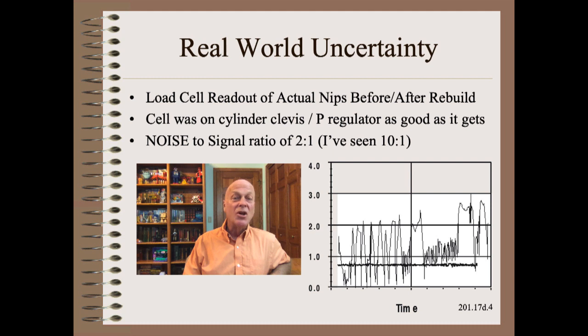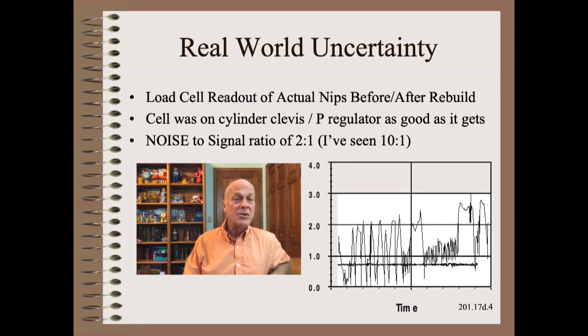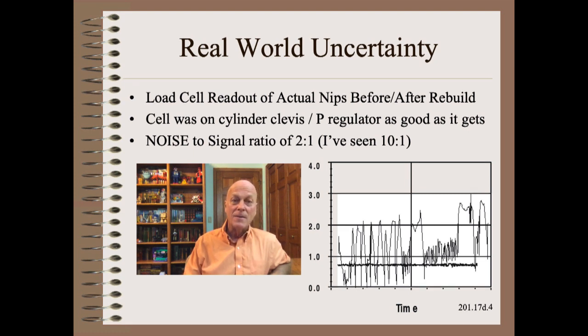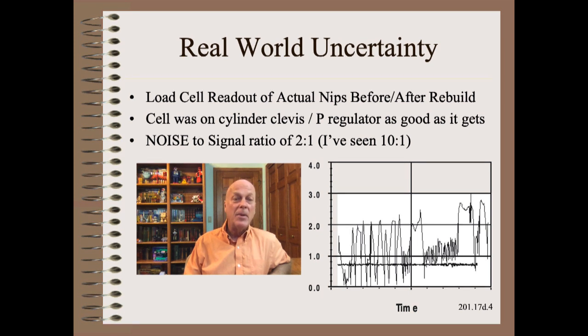Looking at the load on a cylinder clevis as read by a load cell — note that the pressure regulator, which is already a closed-loop device, was as good as you would normally find on industrial equipment. In this example, we would not talk about signal-to-noise ratios. Here, the noise is bigger in size than the signal, roughly 2 to 1. This example, by the way, is one of the most common winders in one of the most technologically mature of the web industries: the secondary arms on a paper machine reel.